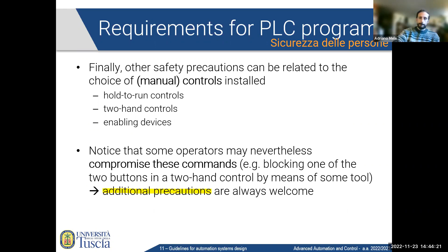Okay, here you have a description of this kind of controls. So hold to run controls: continuous actuation of the control device is required. Two-hand control can be of different types. First, concurrent action by both hands, so continuous concurrent action during the hazardous condition. This is used for presses again.